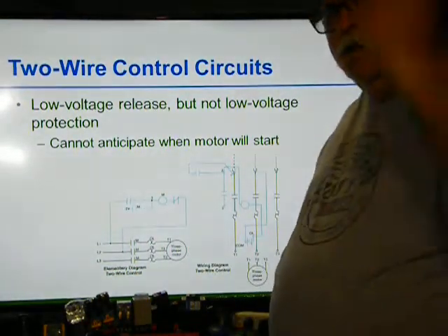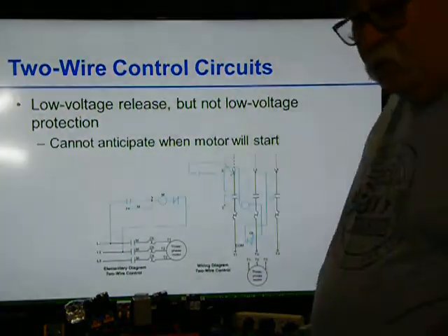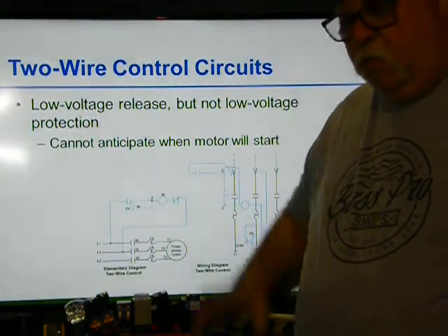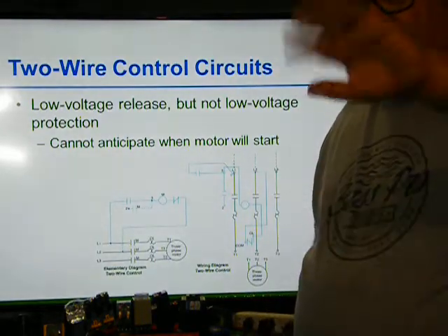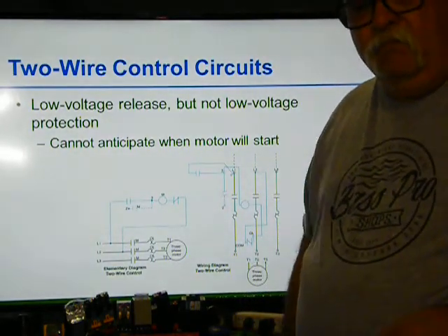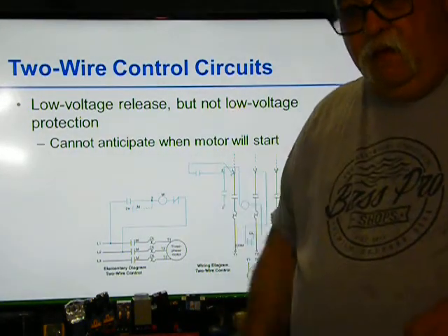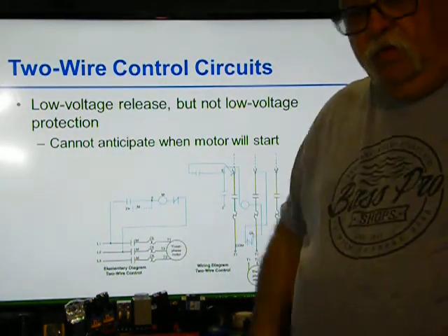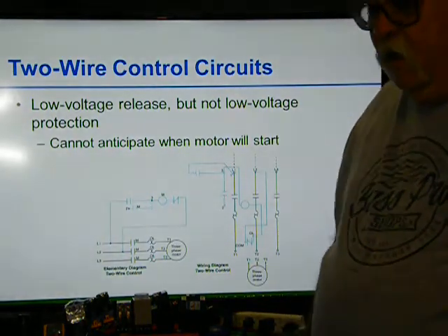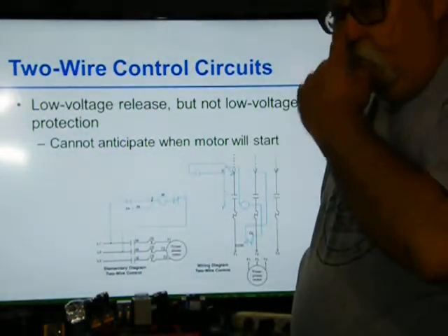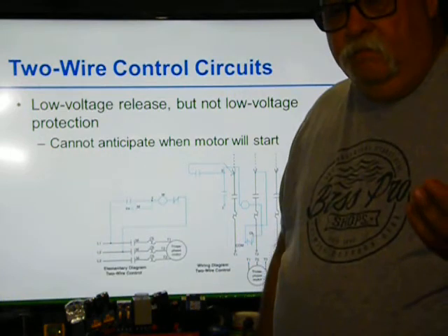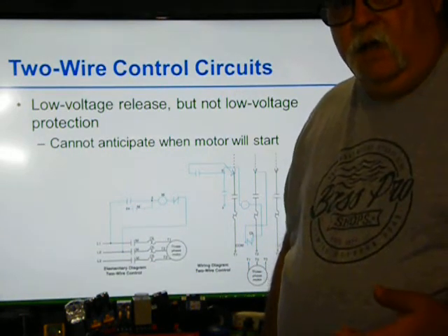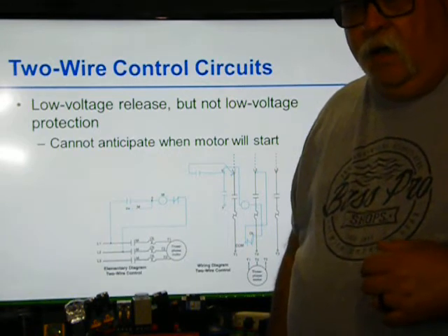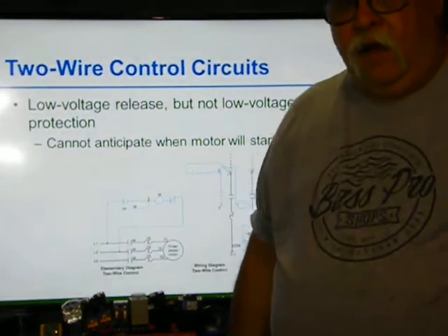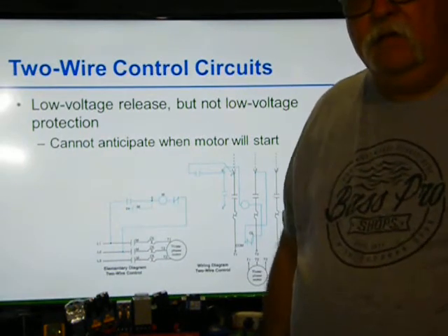Because you're in there working, somebody comes in and says, hey, why is this off? I was working in an area and turned some breakers off because I couldn't put a lock on the panel. I taped them all off and put a tag on the inside. Somebody went over there, opened the panel because they lost power in the room, pulled the tape off, and turned the breaker on. They weren't supposed to have access to this panel. That person could have almost lost his job because he did something he wasn't supposed to do. There are some stupid people out there who say, hey, why is this off, and don't ask. They just turn it back on because there's no tag.